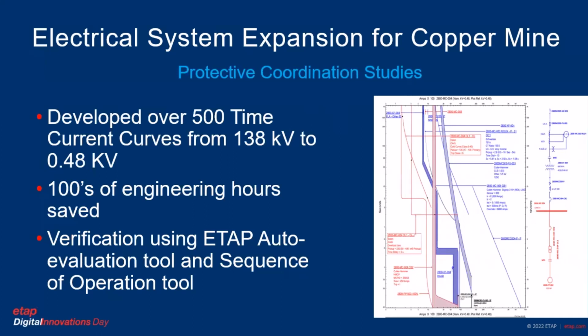Having a tool like ETAP saved us hundreds of engineering man hours, as we were able not only to create the TCC curves, but also verify that our protective device settings were correct. We used the ETAP Star auto-evaluation tool to check our settings against the industry standard, and the sequence of operation tool to verify proper coordination of the devices in case of specific faults in the system.